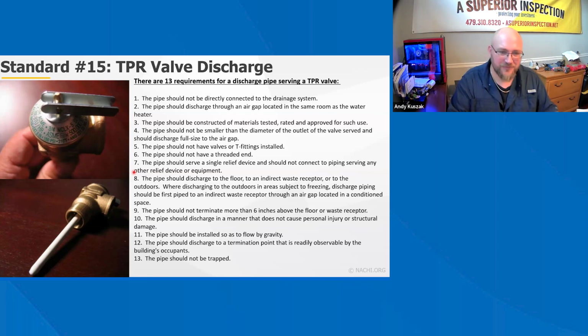And because it was frozen on the outside, that water was not able to discharge. It was just that the TPRV valve was leaking, so it wasn't activating, it was just leaking. But by the time it got to the outside, the water froze, and all that water was backing up into the system. Luckily, it wasn't causing any problems. But had that valve needed to activate, if the unit started to malfunction, then they would have had a major problem.